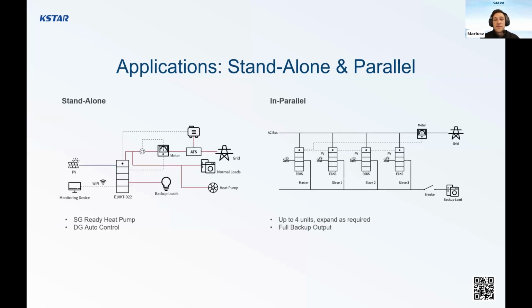As we know, we have different solutions and different households. The new generation is improved by the backup output. And right now we are providing 26 amperes per phase in 3-phase models at the backup output, which is 6 kilowatts. But sometimes we need more. In that situation, we can connect our devices up to 4 in parallel. The 4 in parallel will not only work in an on-grid system, but will also be able to work as an on and off-grid system by connecting to the same power line, the off-grid, the backup, and also the on-grid.